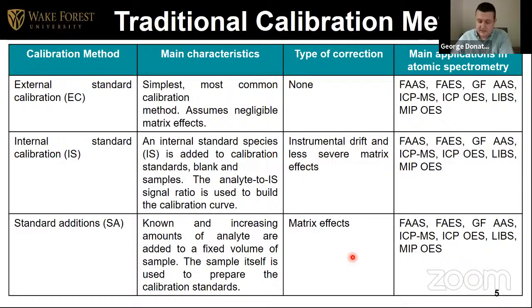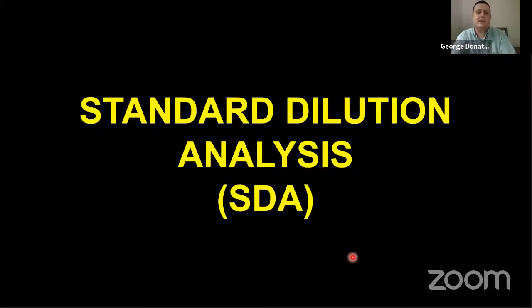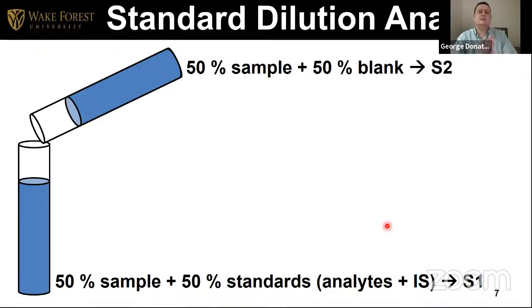So with the new methods we try to develop, one of them being standard dilution analysis, we try to overcome some of the limitations the traditional methods have. I'm going to talk a little bit about standard dilution analysis, which is based on two calibration solutions. The first solution you prepare with half sample and half standards. This is a standard solution which has analytes and has one internal standard. Then you have another calibration solution where you have half sample and half blank, whatever the blank is. Usually 1% nitric acid is what you use.